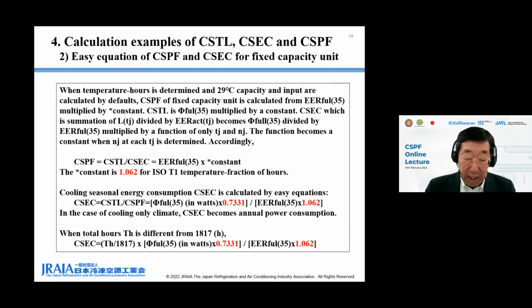This page shows an easy equation of CSPF and CSEC for a fixed capacity unit. When temperature hours are determined and 29 degrees C full capacity and input are calculated by default, CSPF of a fixed capacity unit can be calculated from 35 degrees C full EER multiplied by a constant. CSPF is the sum of load, CSTL, divided by the sum of actual input, CSEC. As shown in the previous page, CSTL is 35 degrees C full capacity multiplied by a constant. CSEC is the sum of actual input.